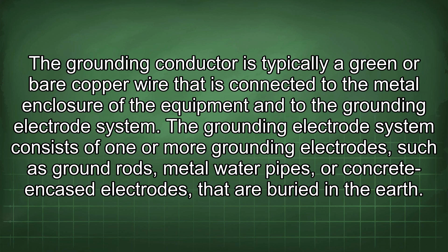The grounding conductor is typically a green or bare copper wire that is connected to the metal enclosure of the equipment and to the grounding electrode system. The grounding electrode system consists of 1 or more grounding electrodes, such as ground rods, metal water pipes, or concrete encased electrodes that are buried in the earth.